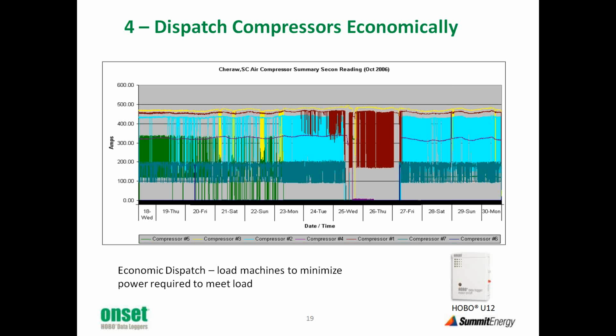But there's another aspect that you should consider. If you have more than one air compressor running at a time, it's really important to be sure the controls are working properly. In this particular case, I have 7 air compressors. So we showed up at this facility with 7 HOBOs, 7 CTs. We put 1 on each compressor. We let it run for a week. That gives us this diagram.